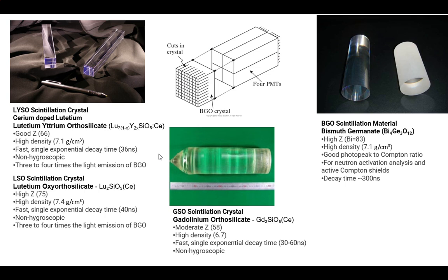Yeah, like I said, long ago they dropped the thallium-doped sodium iodide, and they went to BGO, bismuth germanium oxide, or bismuth germanate, right? You can see, bismuth is one of your big areas here. Germanium's not that big, it's like 36 or something. But bismuth is 83, right? That's a really stupid high atomic number. So that's better than thallium, right, at 81. So bismuth is gonna have a really good cross section for you. You'll catch a lot of photons with it.